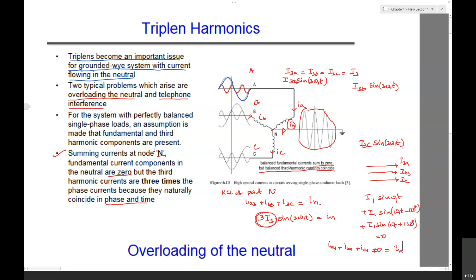But our discussion is restricted to the triplen harmonic currents. When you have triplen harmonics, obviously your neutral is overloaded. That neutral will be overloaded. Here we will also be discussing the condition of perfectly balanced single phase loads in a grounded wye system. We have perfectly balanced single phase loads also.